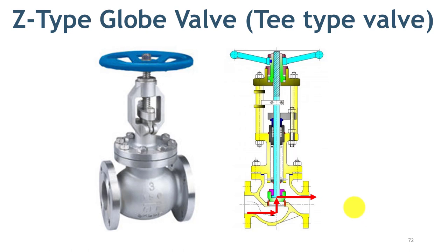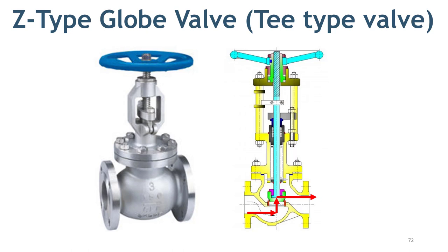You can see that the flow entering the valve has a direct hit on the seat, and the flow is also changing direction while flowing through the valve. These two factors make this valve ideal for high throttling services, and the same two factors make this valve undesirable for pressure-sensitive services. Globe valves used for pressure control are also known as throttling valves and have a specially designed trim to handle the differential pressure.